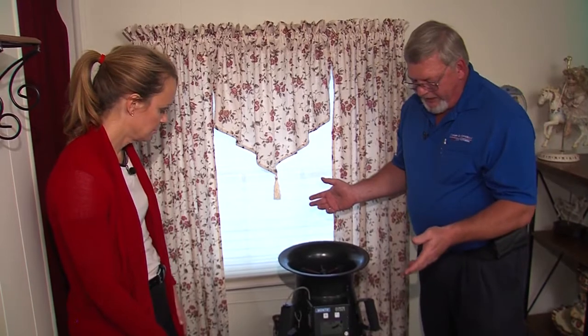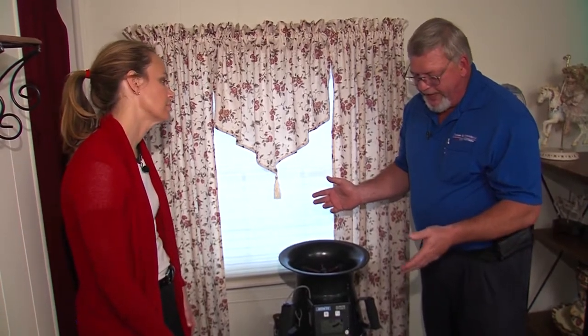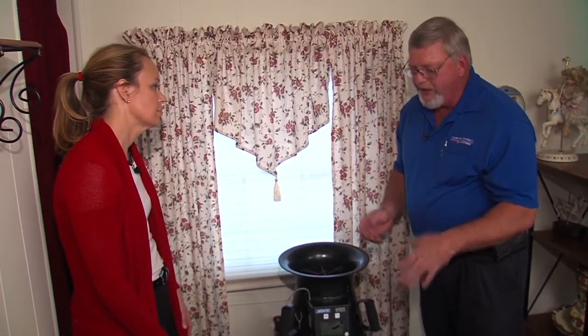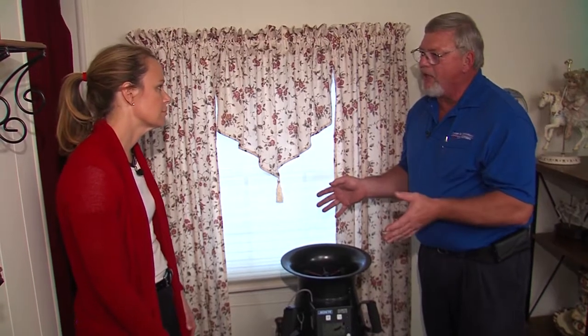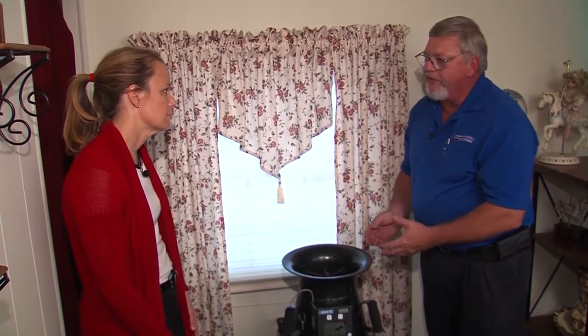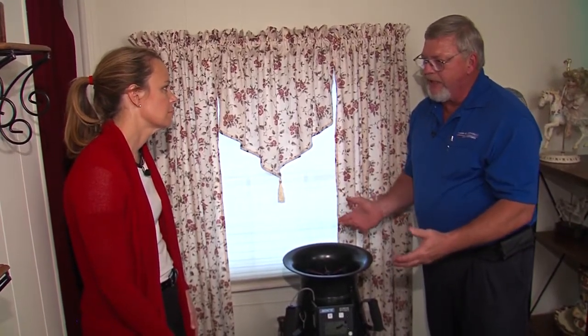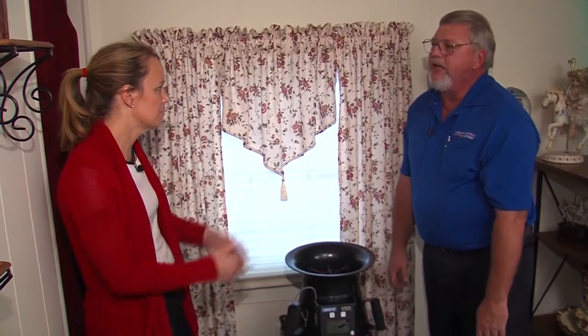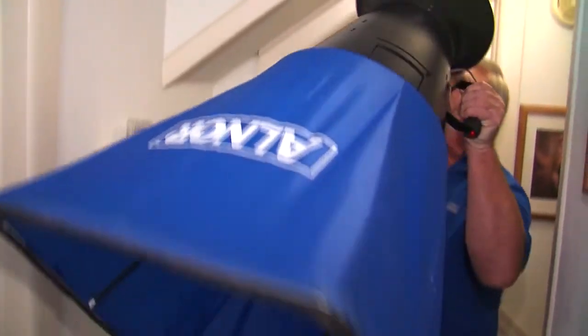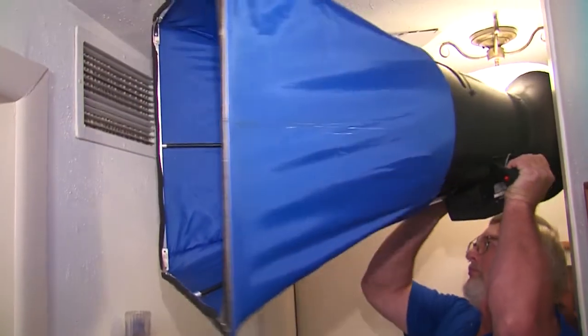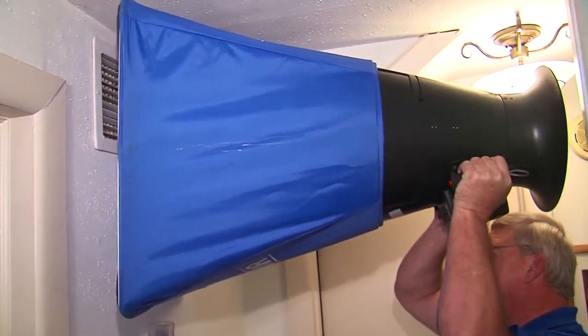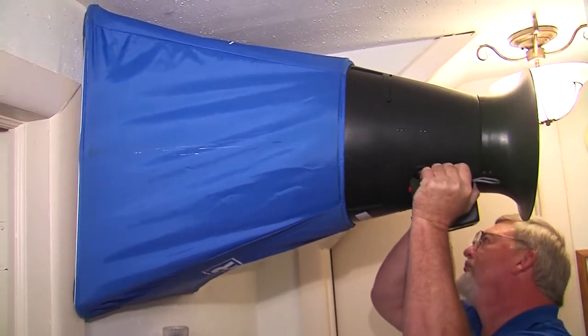As we get into situations where we have a hard time getting over a certain vent, we can take a piece of cardboard and block off this to get that airflow through there to get the maximum pressures that we need coming out of that. Because you want a tight seal. Exactly. And it's not just the air that comes out of the system into your room, it's the air that comes from the inside of your room back into the system.